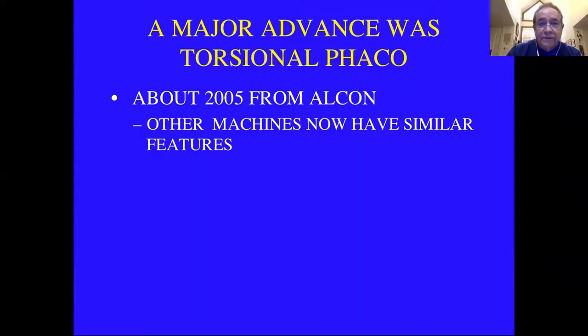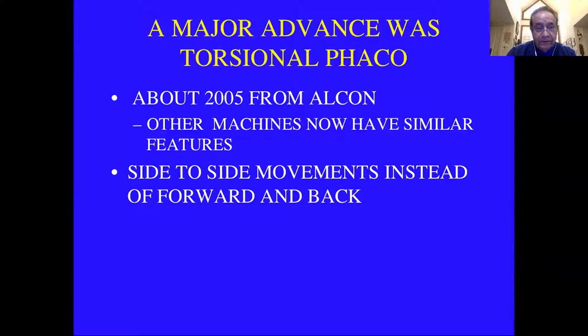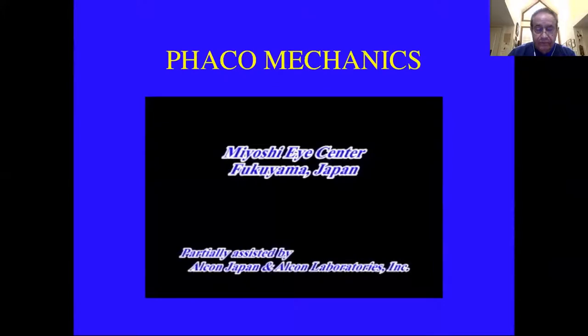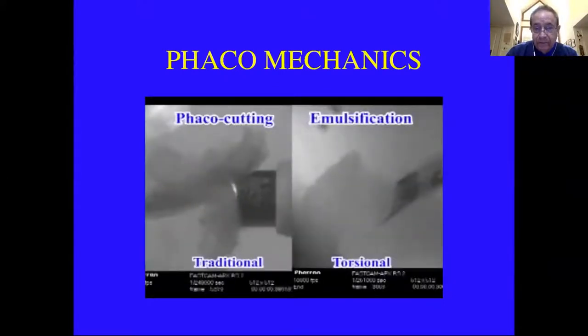A major advance was torsional phaco, invented around 2005. A number of machines now have similar features where you have side-to-side sweeping motions instead of forward and back like a jackhammer. It goes side-to-side, so it doesn't repel lens material — it shaves it, and it cuts on both directions of movement. This shows longitudinal versus torsional motion.